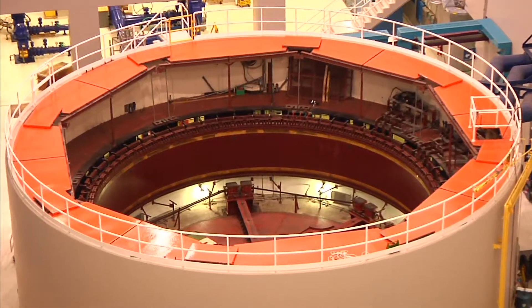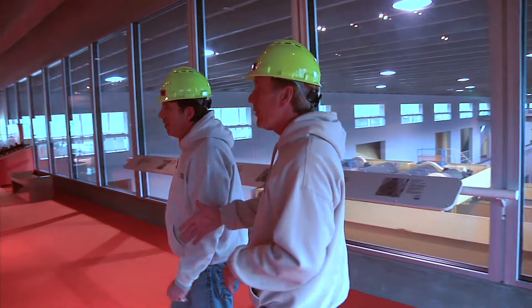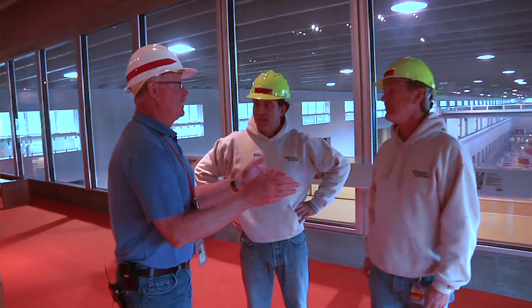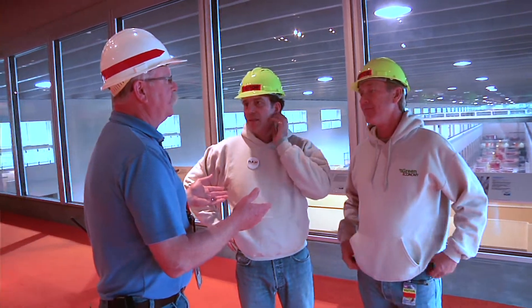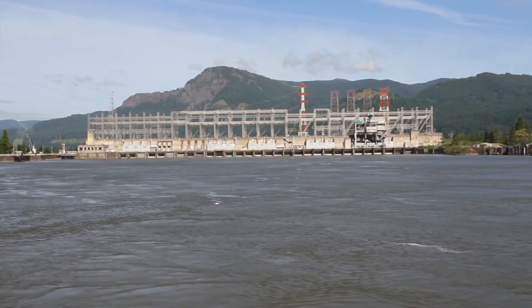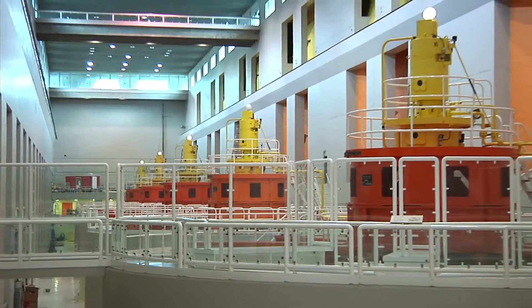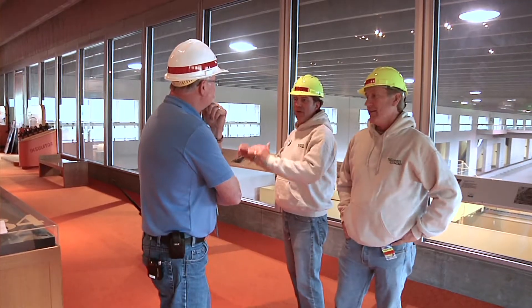Don and I found an expert to explain just how power is made from these dams. Essentially, a dam like this one in the middle of the Columbia is trying to back up water behind it — we have a tailrace that's low, a forebay that's high, and what we call a net head. That head difference gives us the energy to run turbines, so the flow of water through that net head change gives us the energy to run the turbine.